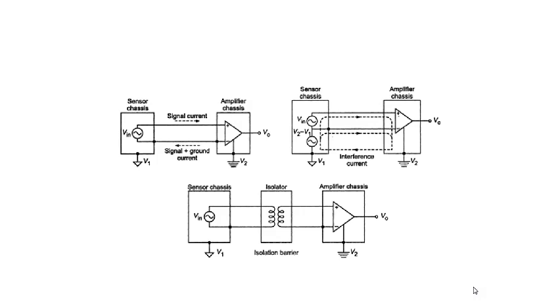In a single-ended system using a common ground, along with signal current there is a ground current flowing that affects measurement. In the differential system, even though the differential amplifier nullifies the common mode voltage from ground differences, there are interference currents that generate noise. The voltage difference V2 minus V1 generates interference current in the cable due to the cable's finite resistance, affecting measurement.